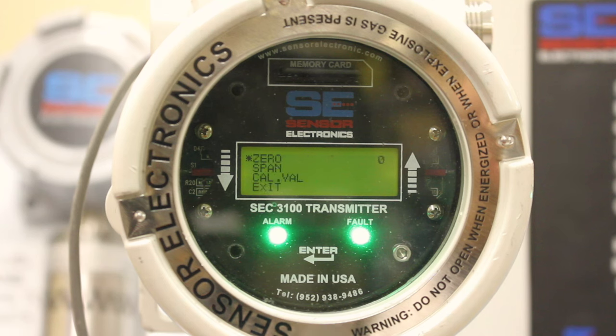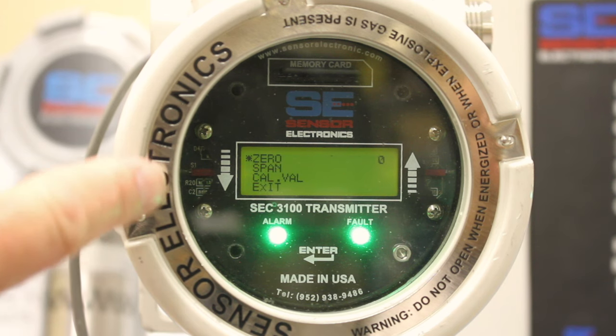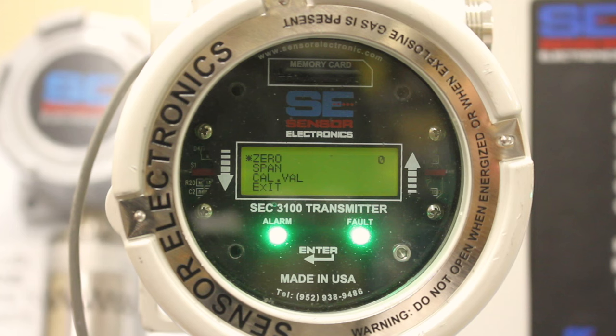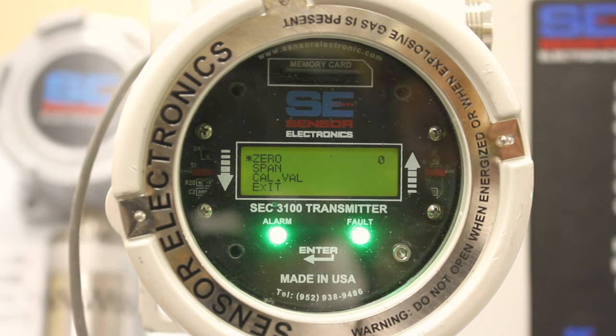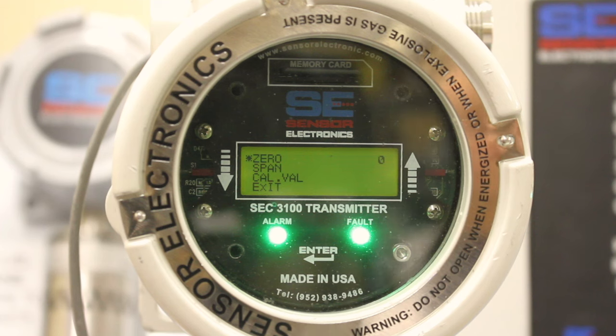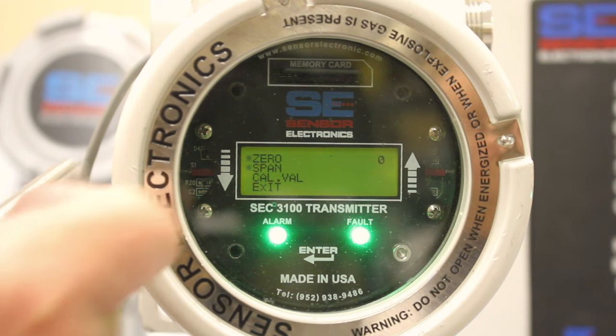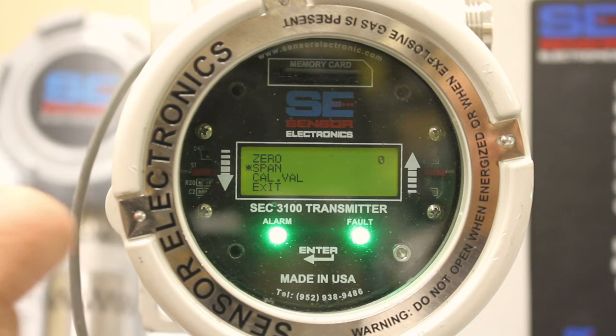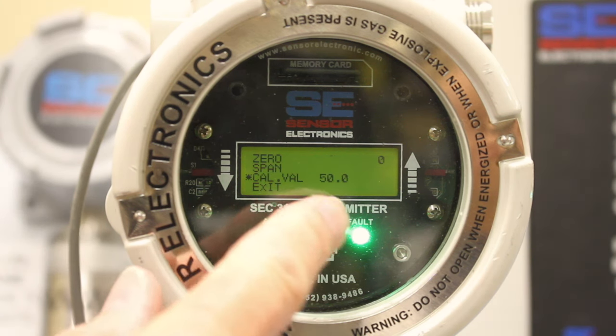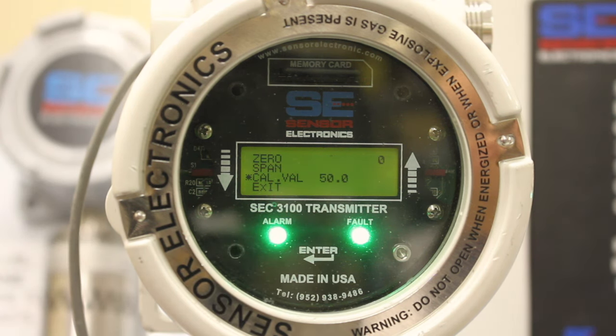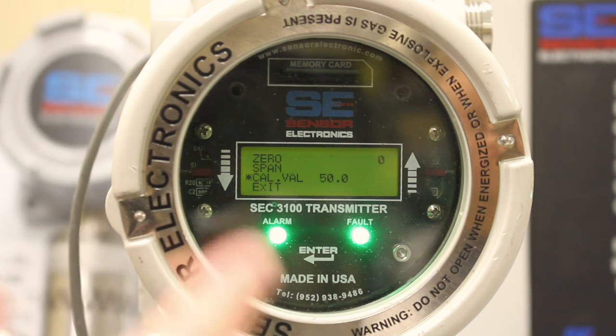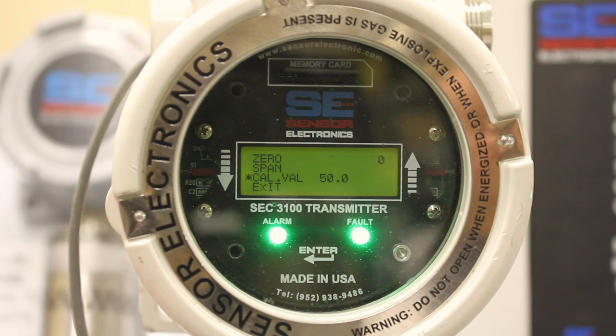So if you select that, this is where you sequence through in either zero or span, or zero and span the sensor. And we've already covered that in a different video, so we'll just go through and show you the different ones. And it shows you the cal value of the span gas that you're supposed to apply to the sensor, which in this case is 50% LEL. So we arrow down to Exit.